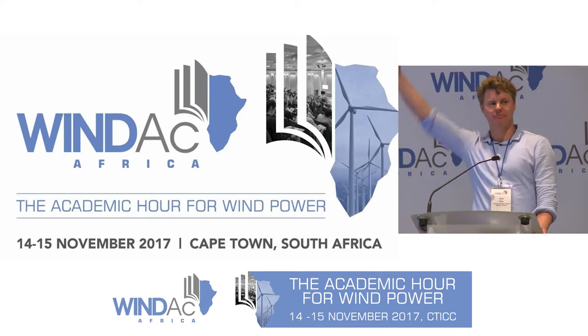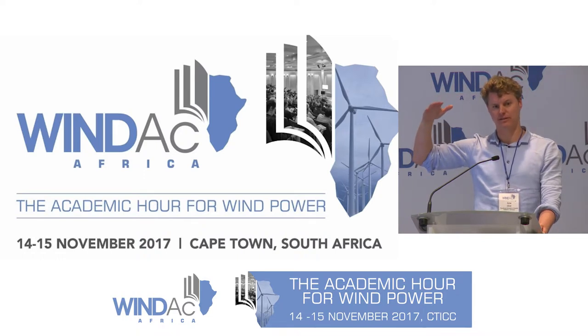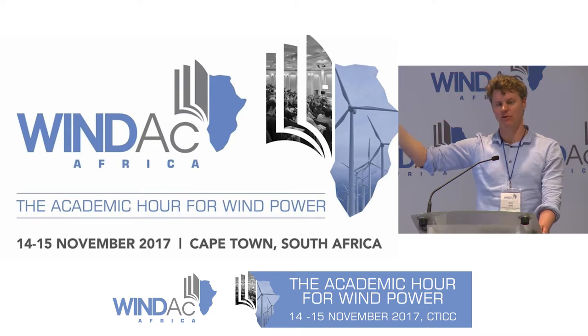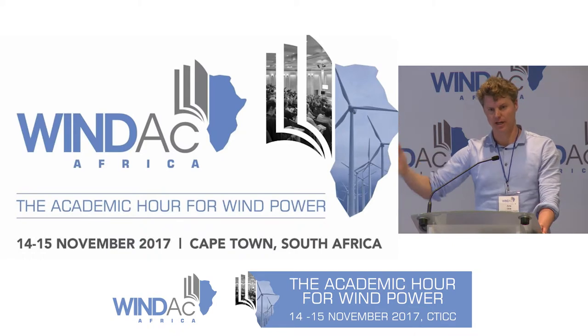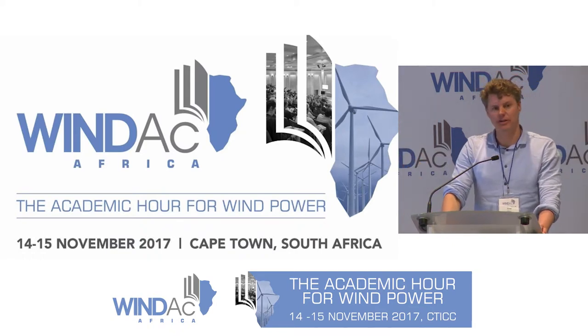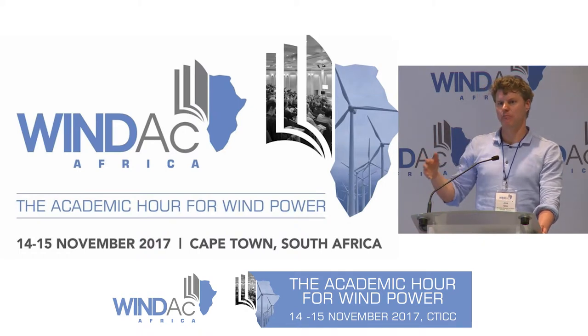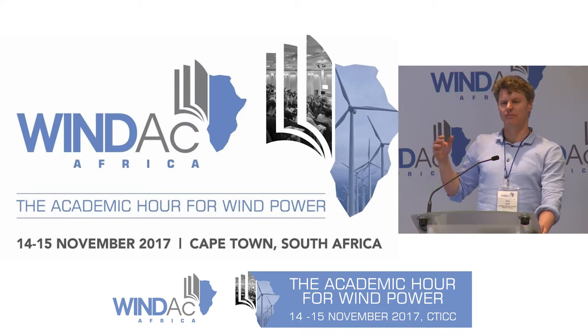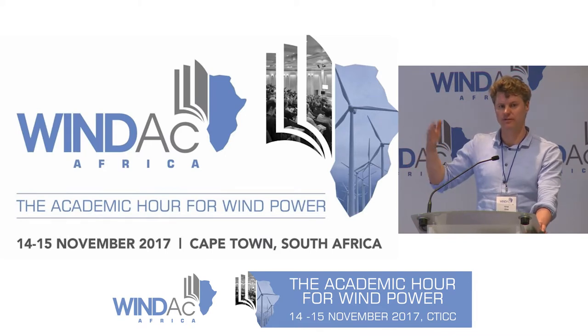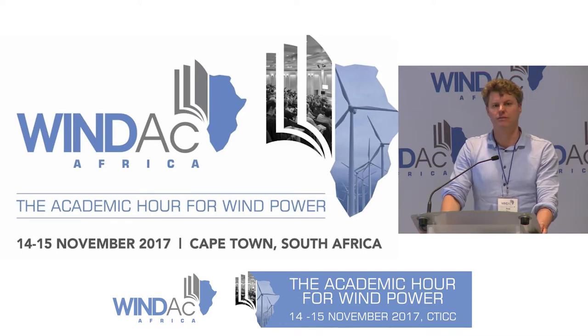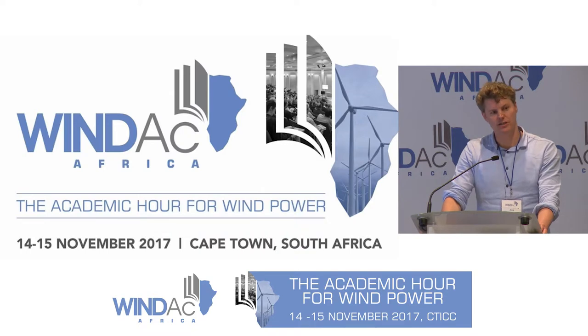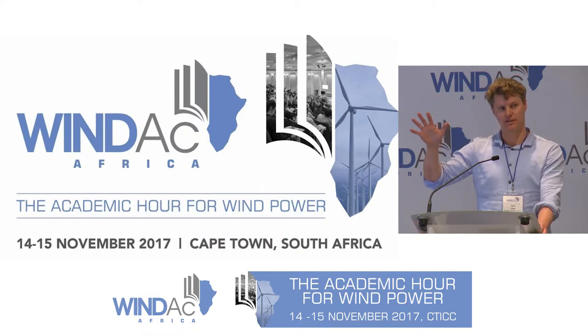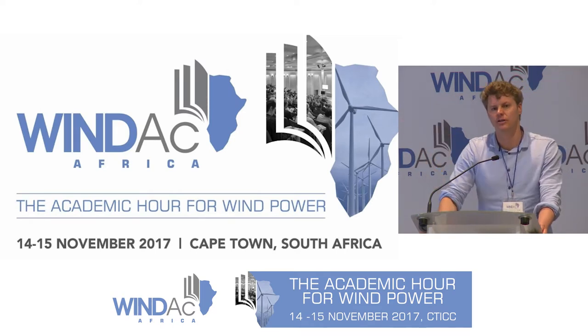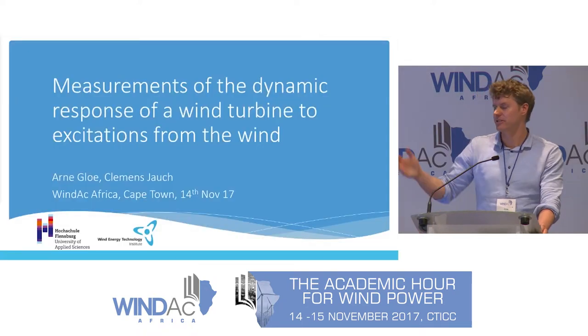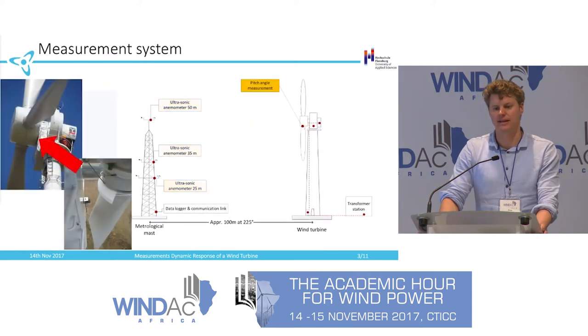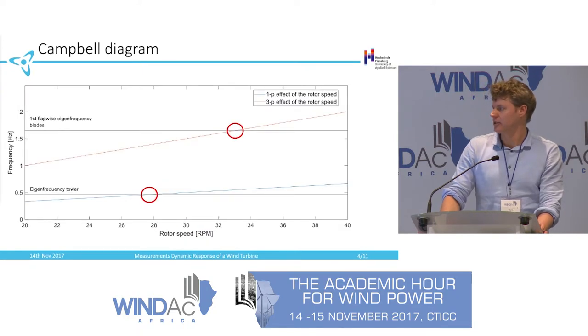So basically, what we see is whenever we approach the critical speed, the resonance speed, our tower starts to vibrate. So it starts to move more and more. And that's certainly something you want to avoid. So basically, what we found during the research is that this turbine seems not to avoid this 1P situation or this resonance situation. And that might be very problematic if we want to control the turbine towards the need of the grid in this situation. So a typical thing you would do to support the grid is change the power set point of the turbine. If I change it with the same frequency as the tower, then I certainly get an additional excitation.